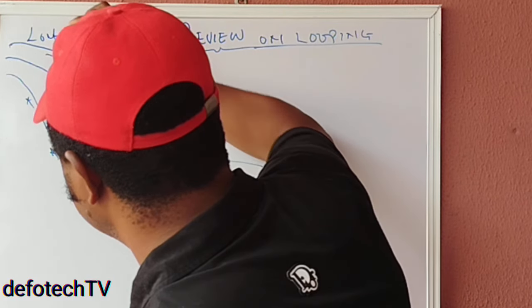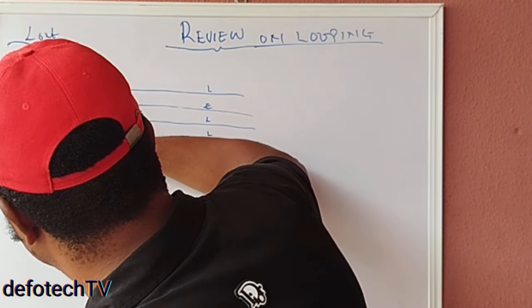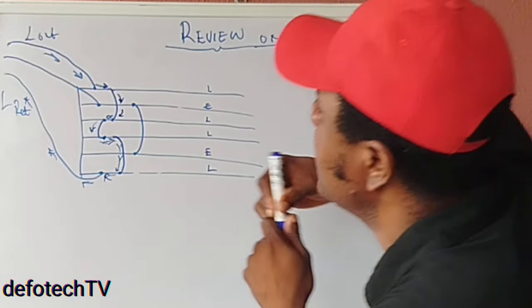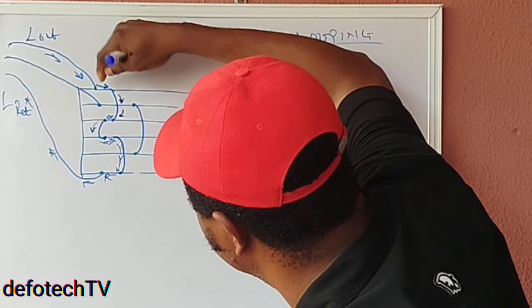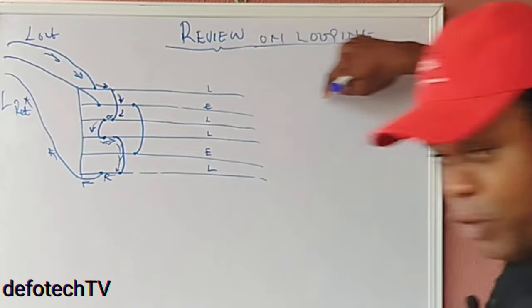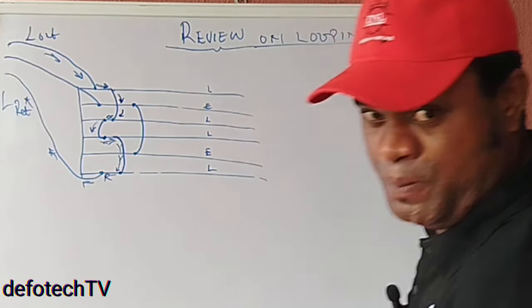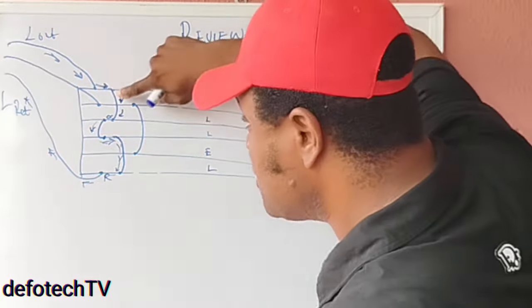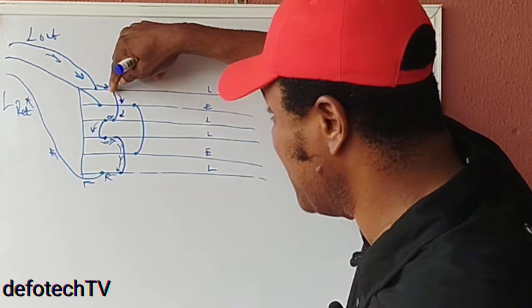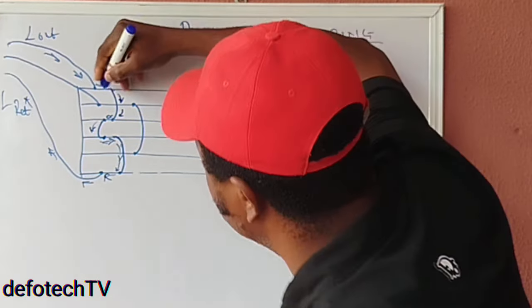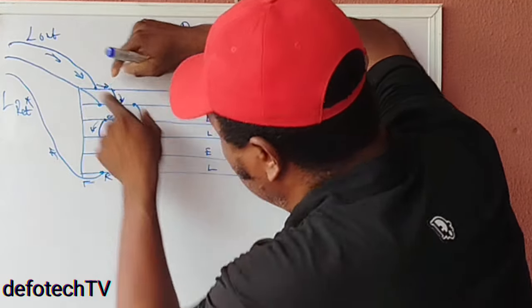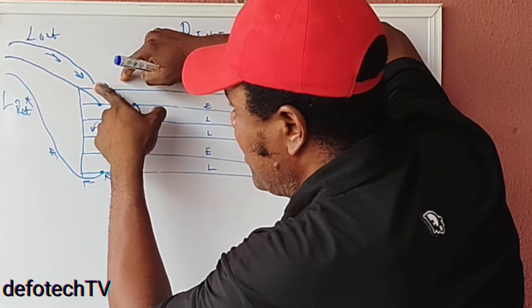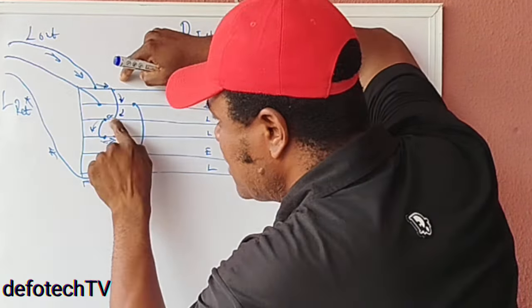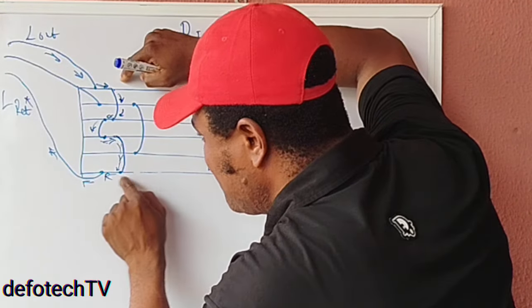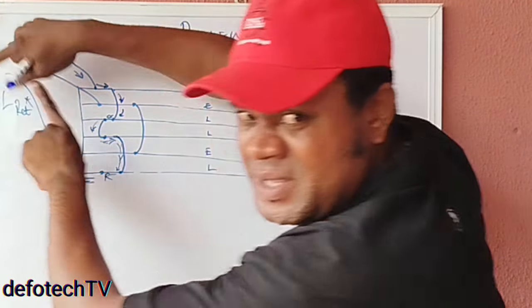Please, you must avoid this error. Like I explained, let's assume this is a live out, and this is a live return. It means the power comes here, and it's supposed to flow in without having this loop. This loop is not supposed to be here to alter the movement of current. So you're supposed to have this one out, but because they have this one, it will allow passage of current from here to this one, and this one allows passage from here to this one. This will allow from here, already giving a complete loop.